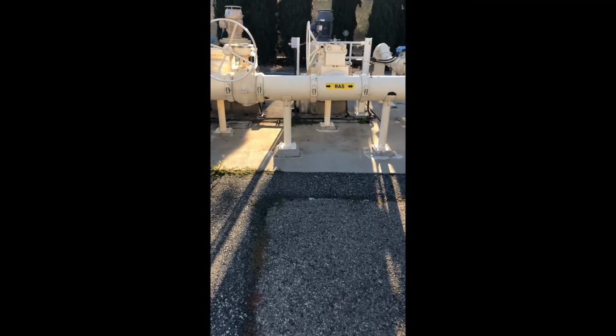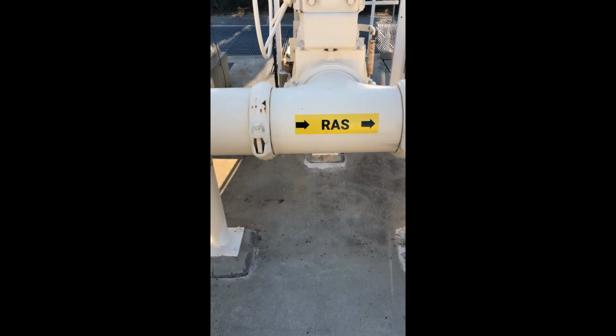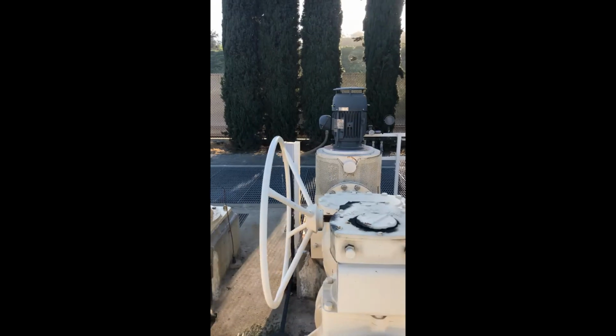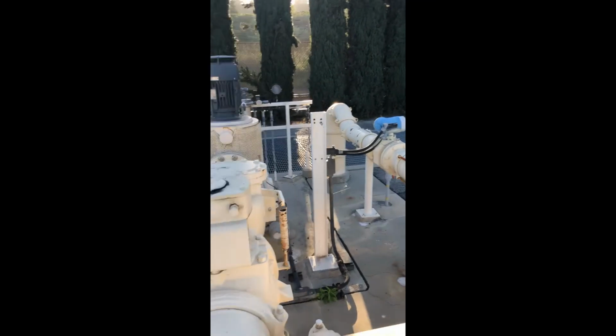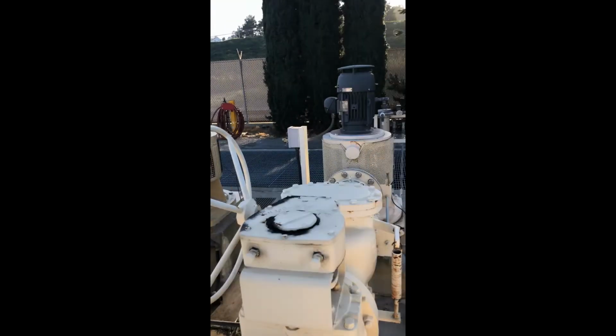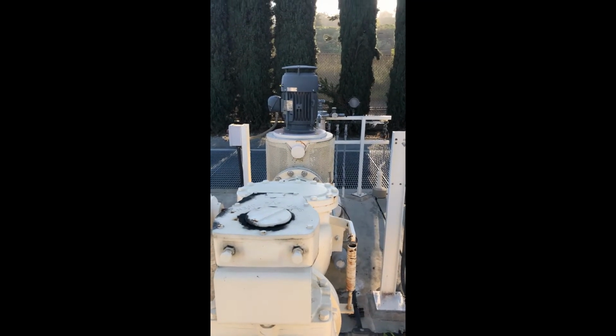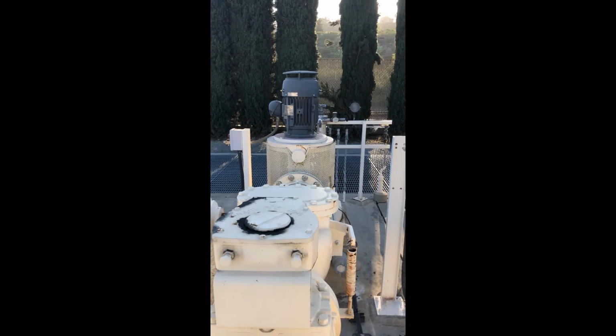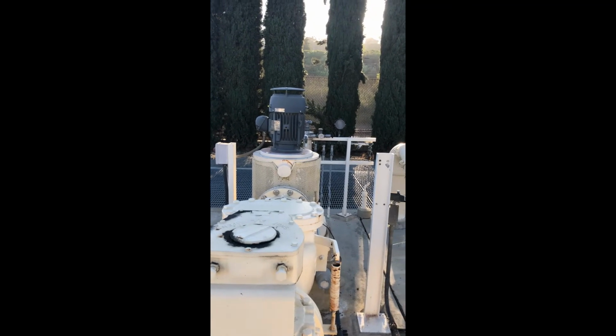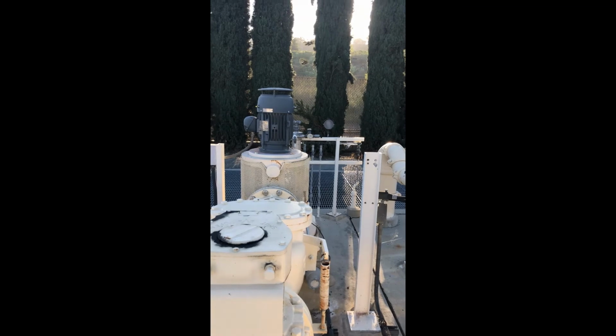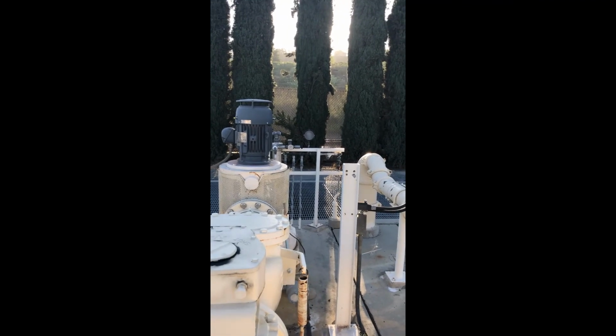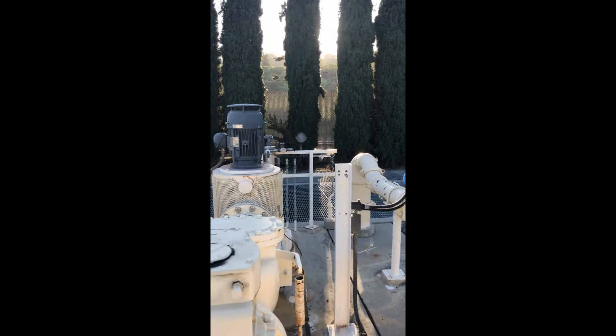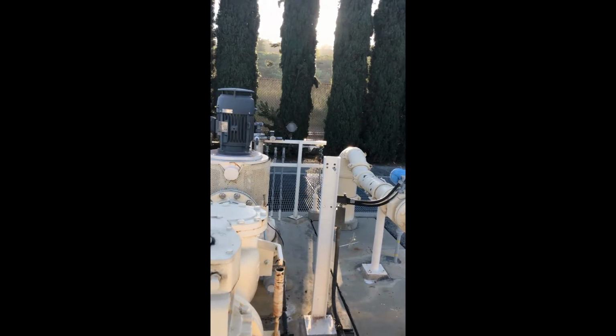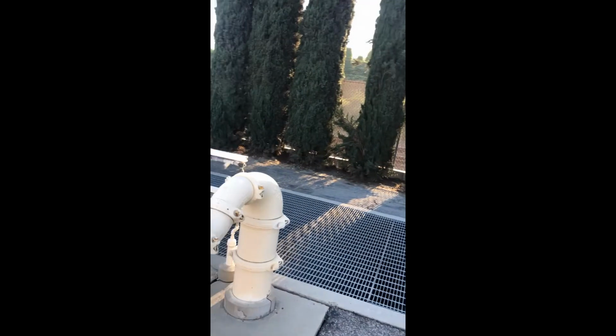These are the RAS, or return activated sludge pumps right here. The variable frequency drives are going to automatically return the correct percentage of activated sludge proportional to the amount of flow that comes to the plant. So the more flow that's coming through this plant, the more of this sludge we've got to return and keep the bugs going here. Okay. So there's quite a bit of closed loop control here.